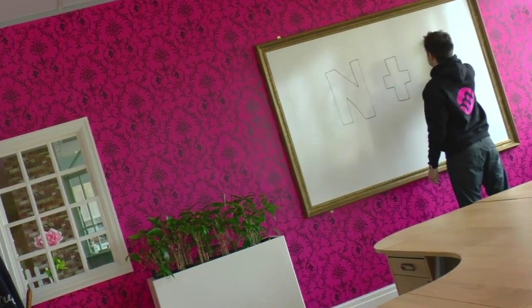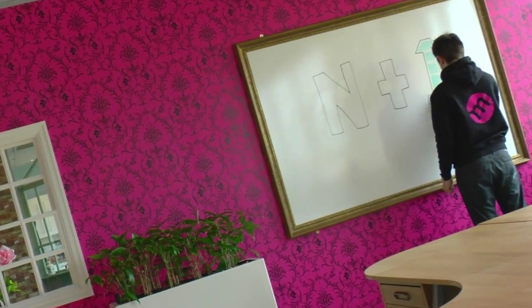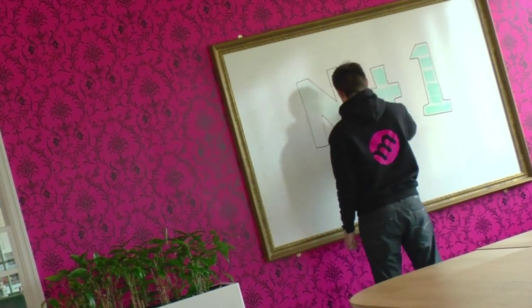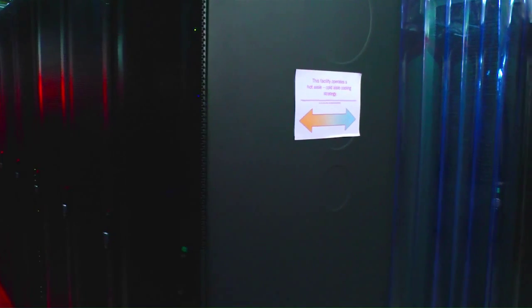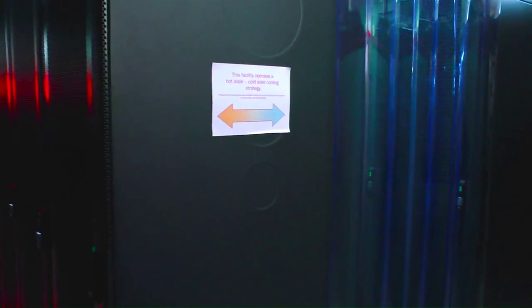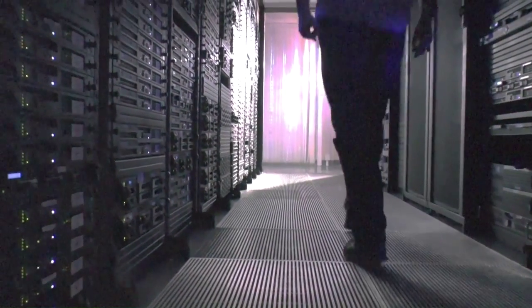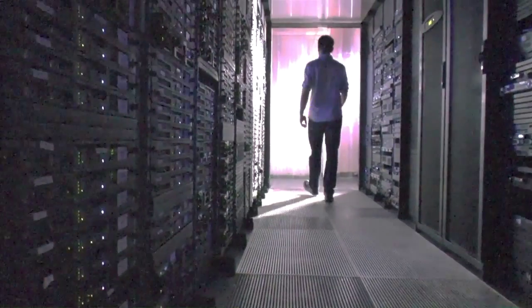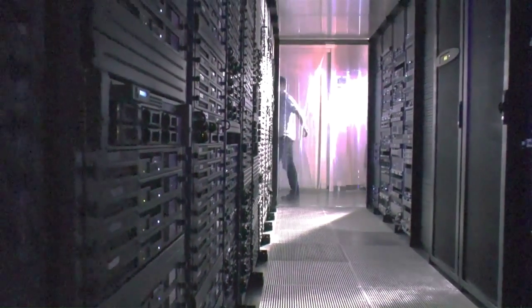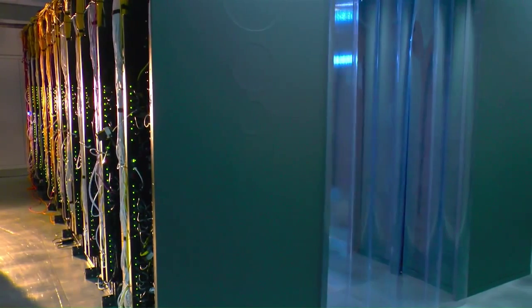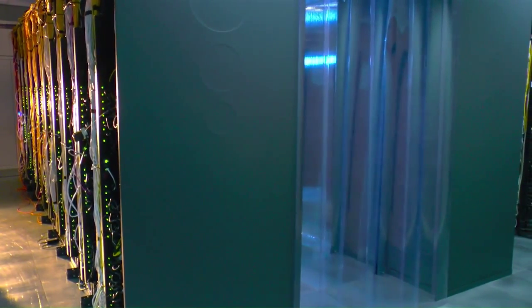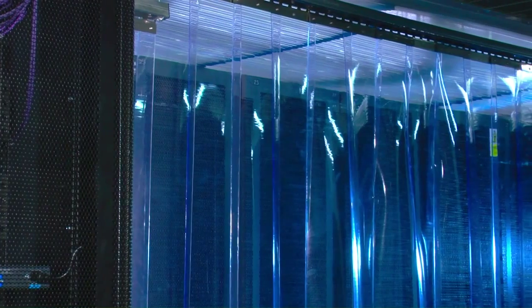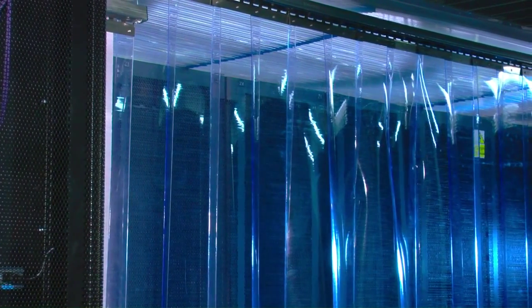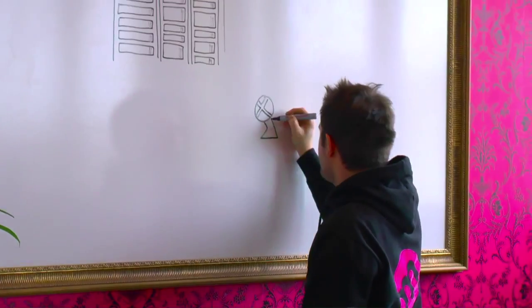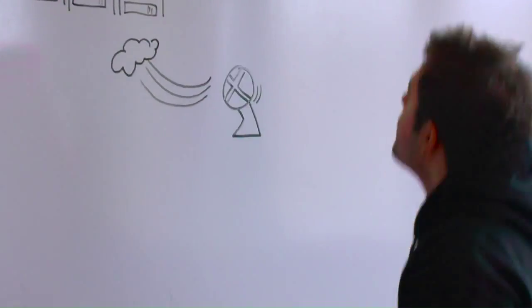We have N+1 air conditioning, so we've always got at least one standby unit ready to take over, should one fail. Also, we were one of the first UK data centres to embrace cold aisle containment. Cold aisles are contained, so the only way for the air to get out of the cold aisle is by being drawn through the server by its own cooling fans. This is not only the most stable way of keeping your data at the right temperature, but also the most environmentally friendly way of cooling a data centre. Cold air is delivered through an underfloor void of nearly 1 metre to keep it separate from warm air.